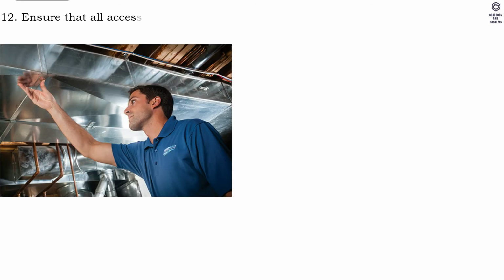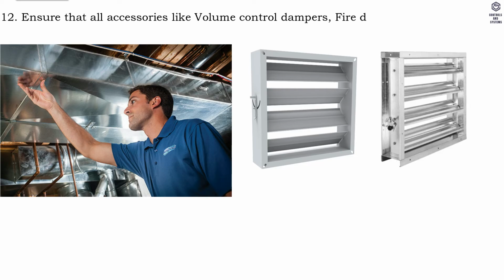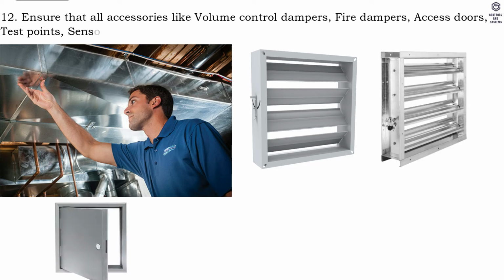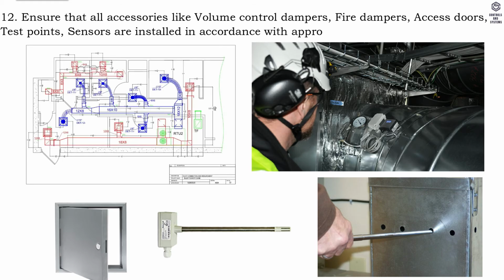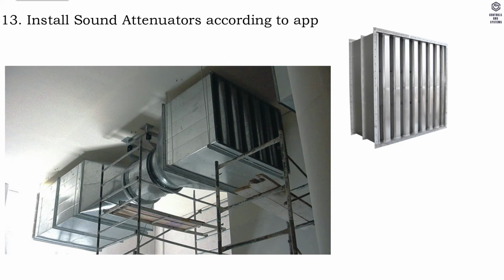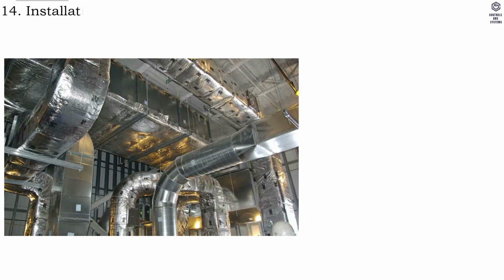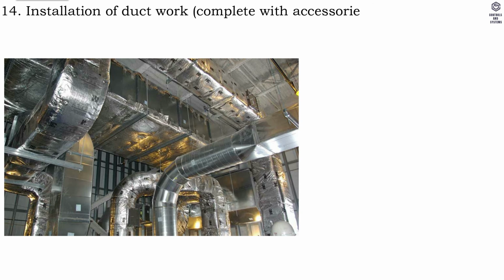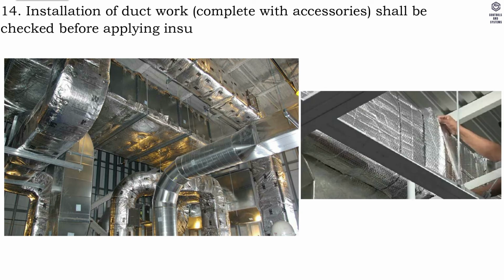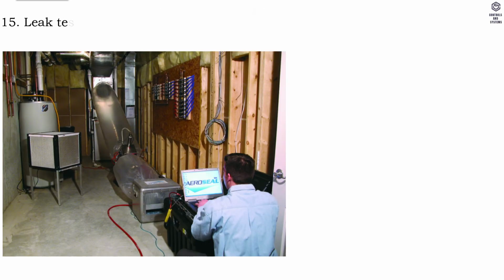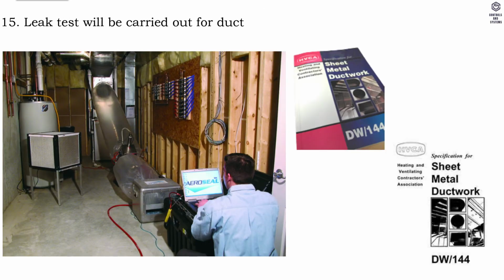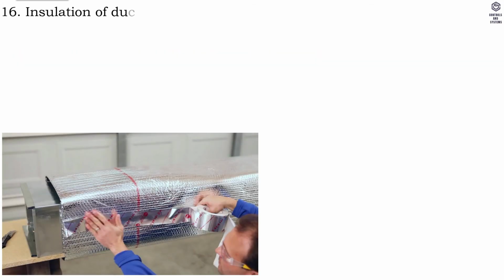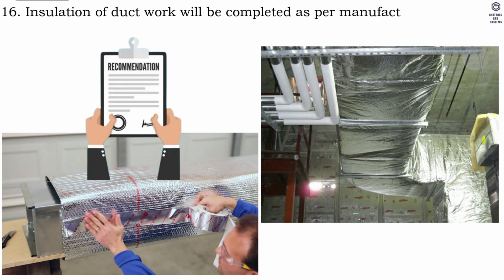12. Ensure that all accessories like volume control dampers, fire dampers, access doors, test points, sensors are installed in accordance with approved shop drawings. 13. Install sound attenuators according to approved shop drawings. 14. Installation of ductwork, complete with accessories, shall be checked before applying insulation at joints. 15. Leak test will be carried out for ductwork as applicable in DW144 standard. 16. Insulation of ductwork will be completed as per manufacturer's recommendations, copy enclosed.